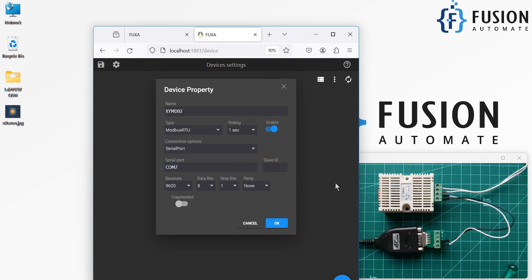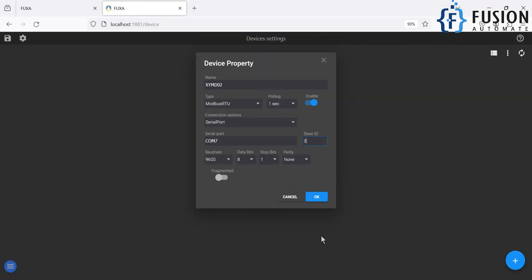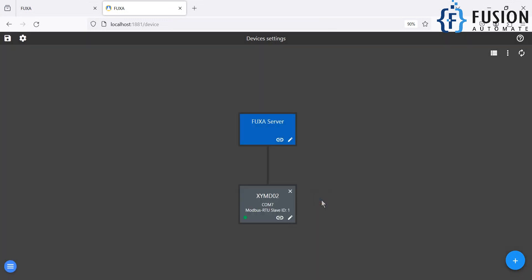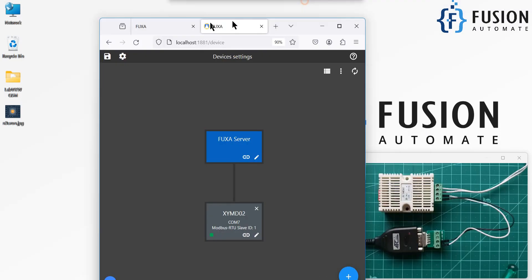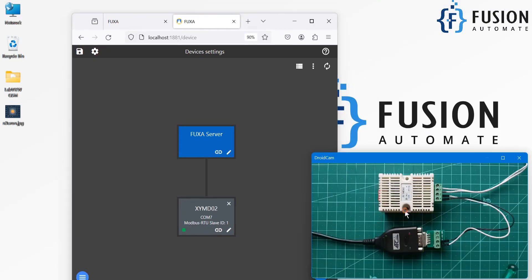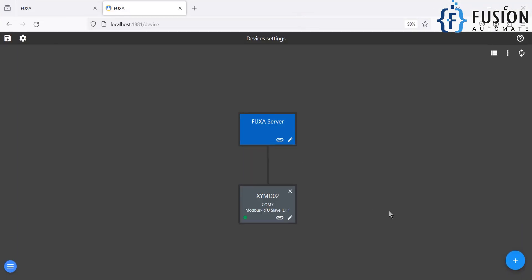Slave ID of this device is 1, so I am going to provide 1. The baud rate 9600, data bit 8, parity none, and the stop bit 1. So that's it. I am going to hit OK. You can see it is green. It is green, it means it is able to connect with this device. So we have successfully set up the Modbus serial device connection in the FUXA SCADA.